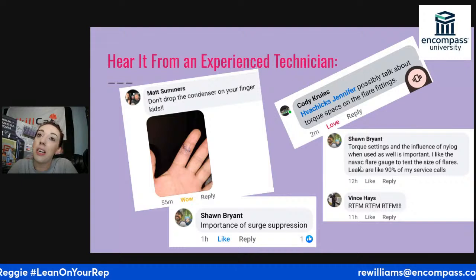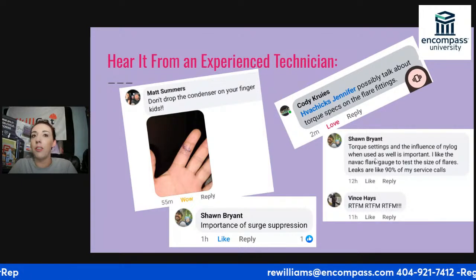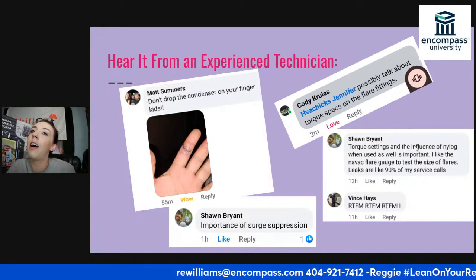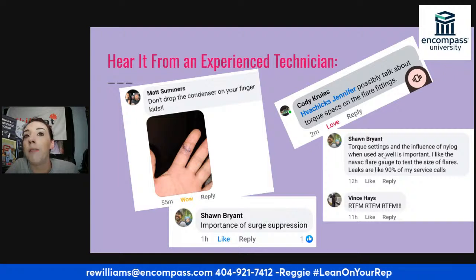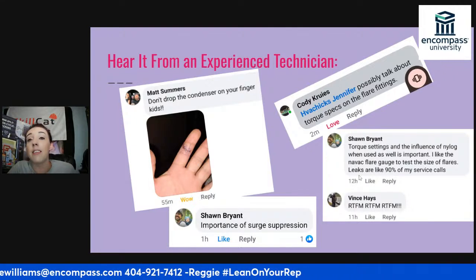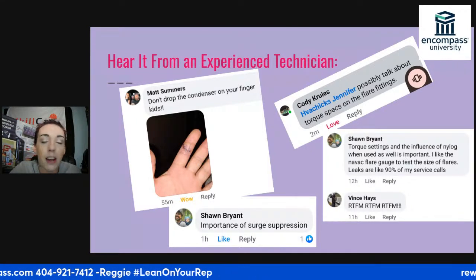And then we have torque settings. I didn't get into this earlier on purpose. Torque settings and the influence of Nylog when used are important. I like using a flare gauge to test the size of the flares. There are flare gauges out there you guys can buy.